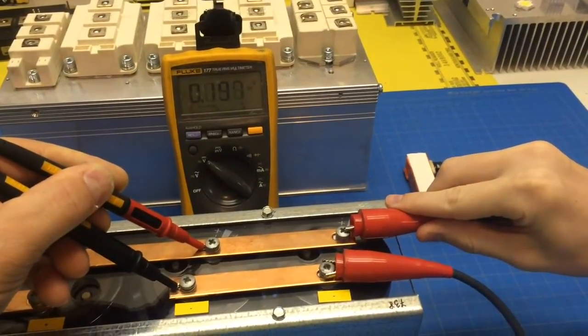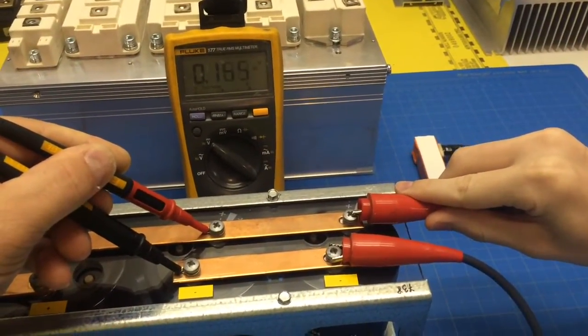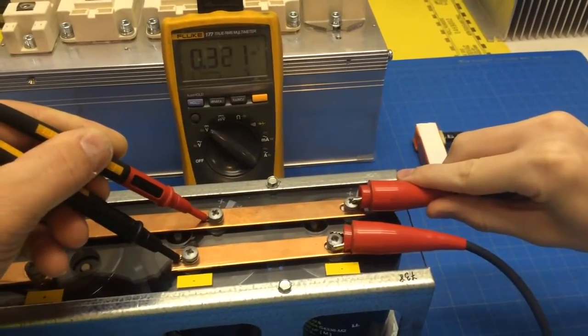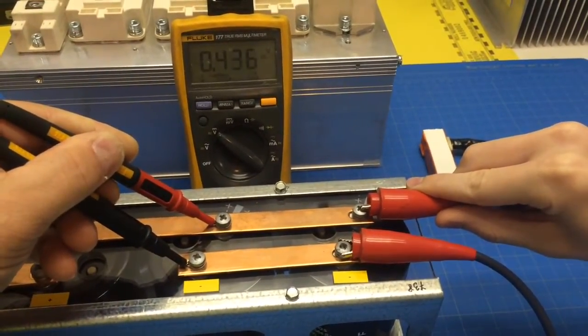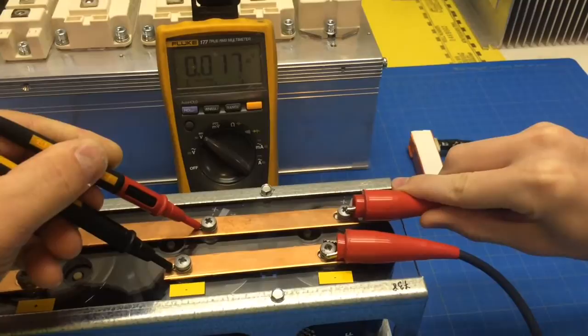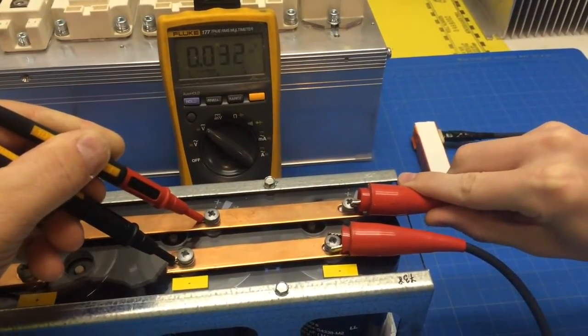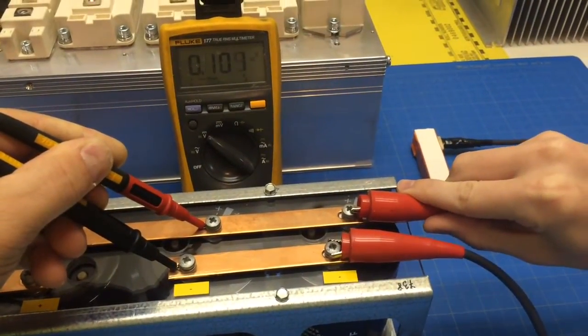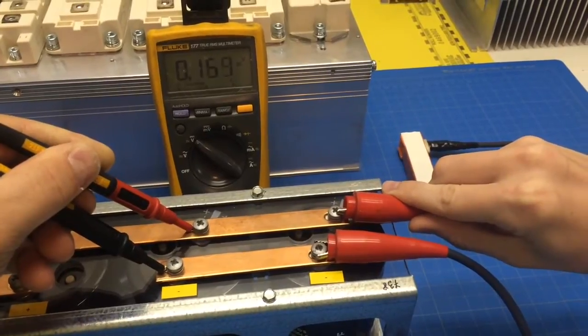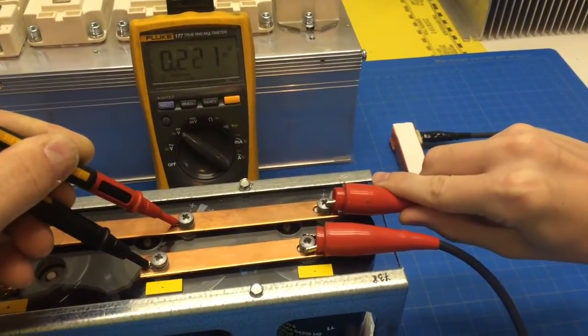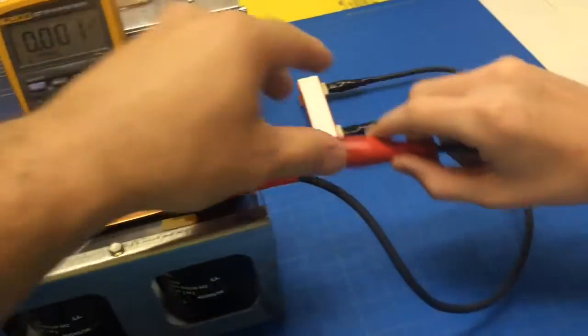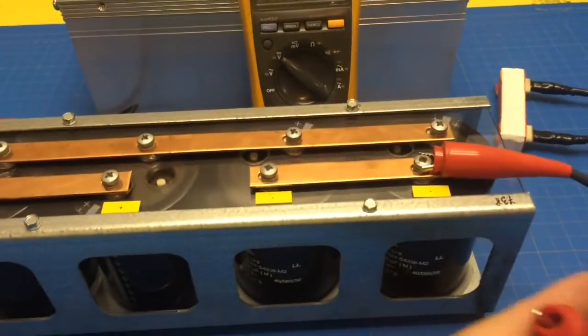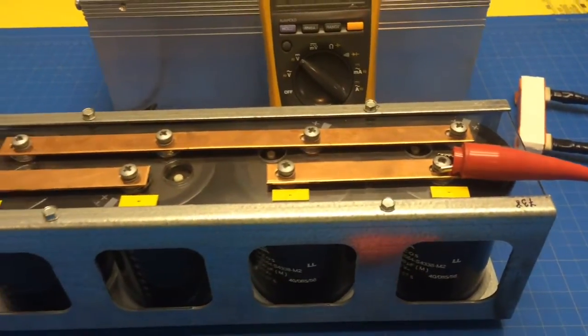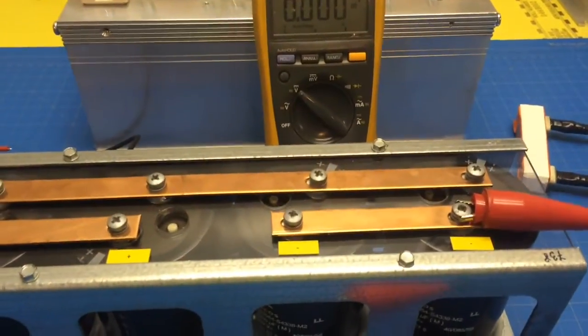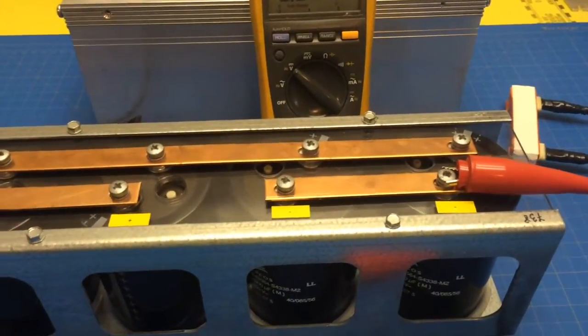Now we can see that pretty quickly drains it, not so fast to actually damage the capacitors or to cause a spark and arc. A lot of people just put a screwdriver across a single cap or a small cap. But if you have a capacitor bank and they're large, it's best to use a high wattage resistor. Make sure you're well insulated. Again, this is just a small cap bank, but on a large one, some elevator drives have 32 capacitors in there, 700 volt drives.